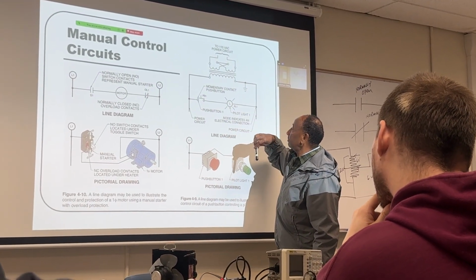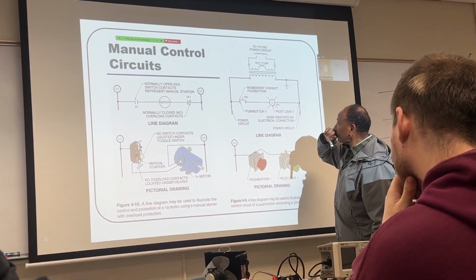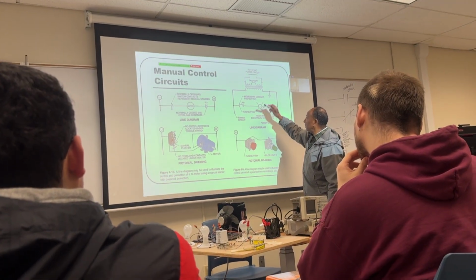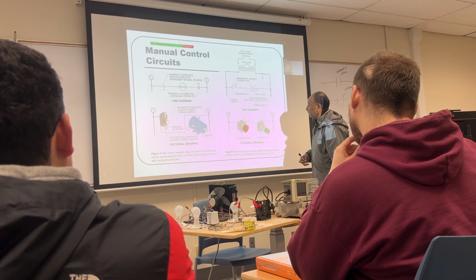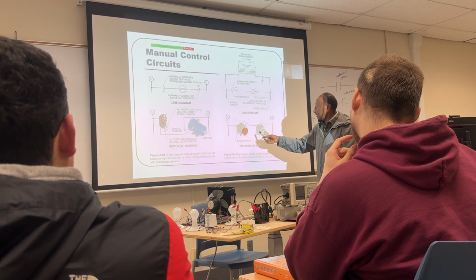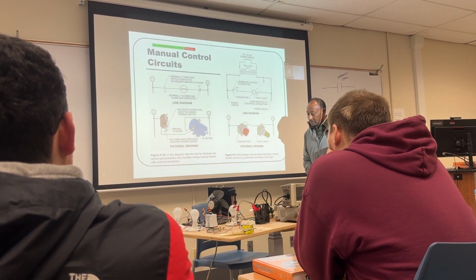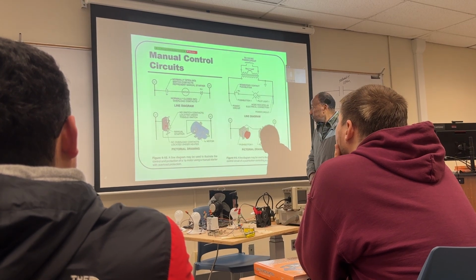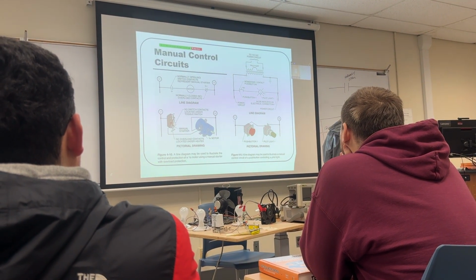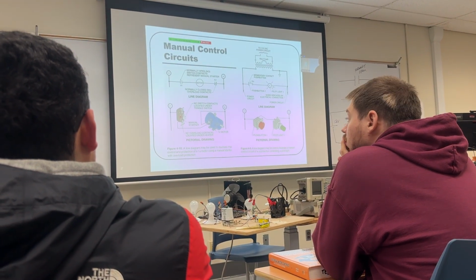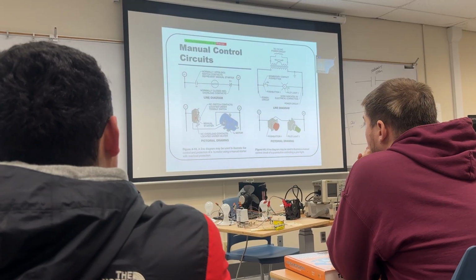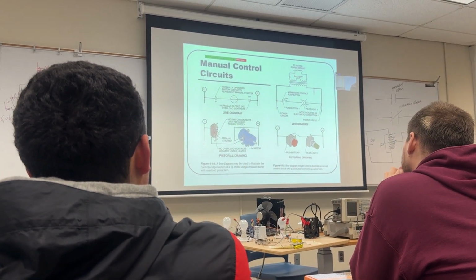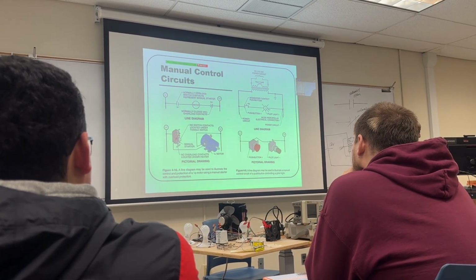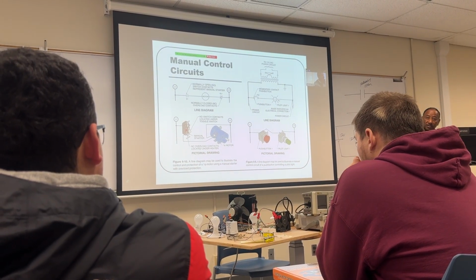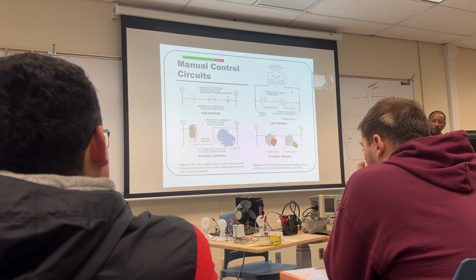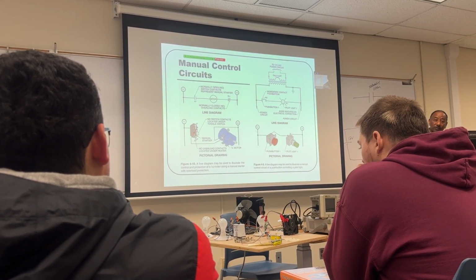So this is, you have a magnet, push button switches here. When you look at the body of the relay, on the case, it'll tell you how many volts it can handle, right? It'll stamp it on there. A lot of them we have can handle up to 120 volts. There are some older ones at 200 to 220 volts.